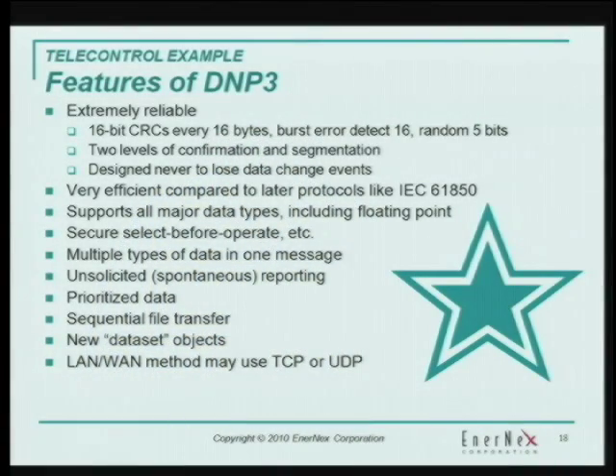So it's very reliable, but still more register based. It doesn't have an information model per se - you still have vendor A and vendor B. Vendor A may represent voltage in register number 23 in volts, but vendor B may put voltage in register 47 and it may be in kilovolts. So still quite a ways away from the interoperability and self-discovery we see in other protocols in other industries.